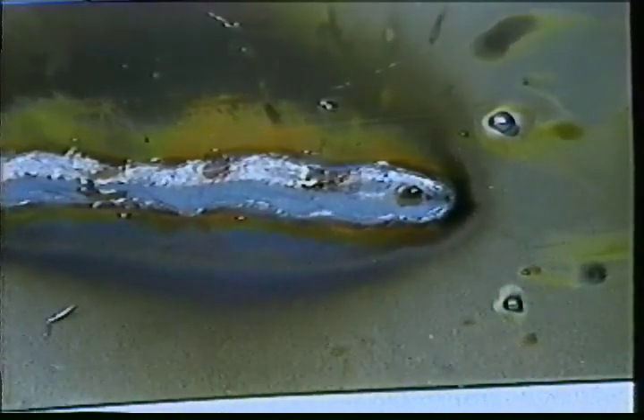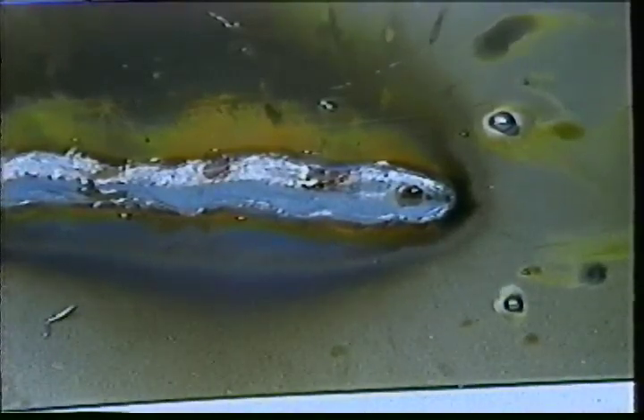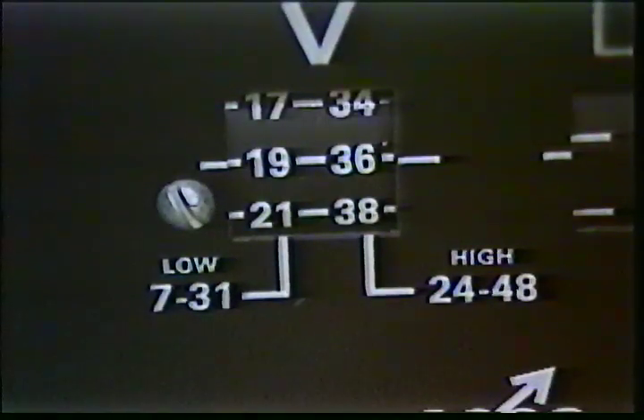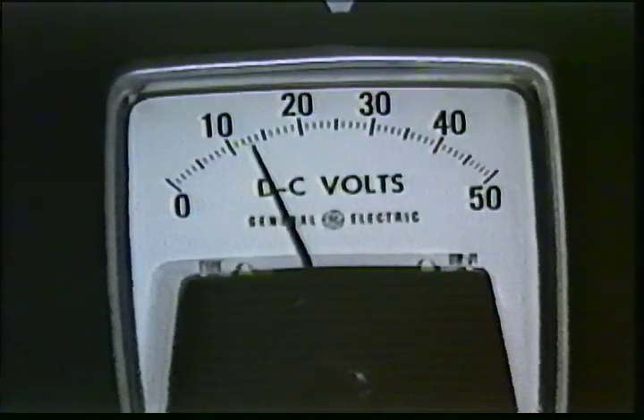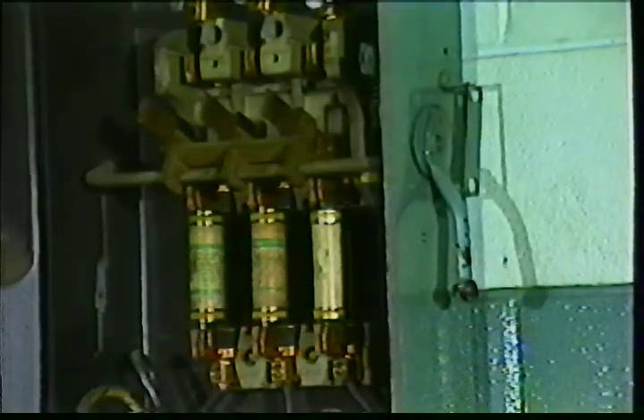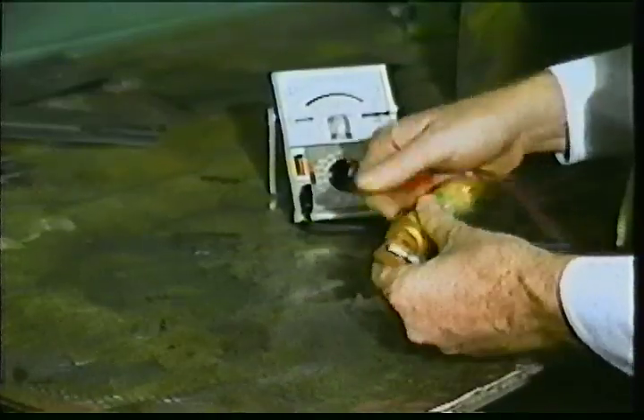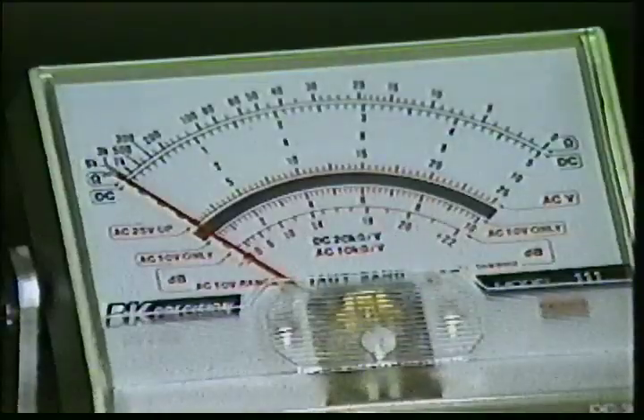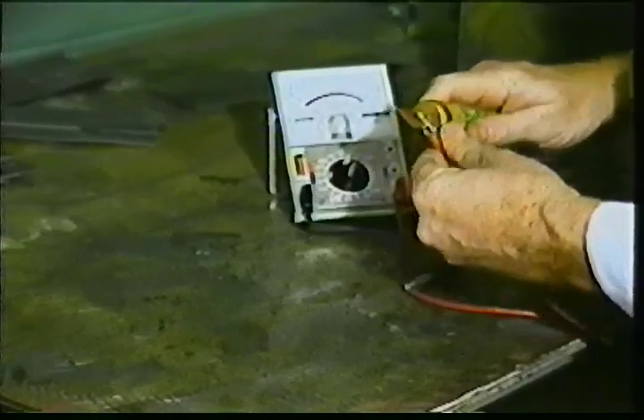Spatter can indicate high voltage or other process-related trouble. However, in this case, the power source is set for 19 open circuit volts, and the voltmeter indicates 13 load volts. This may indicate a single phasing condition. A qualified electrician should be called to check each of the 3 primary fuses. Primary power is shut off and the fuse removed. The continuity check shows that the fuse is open.